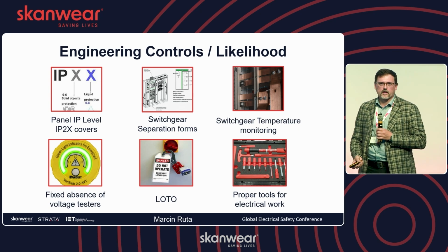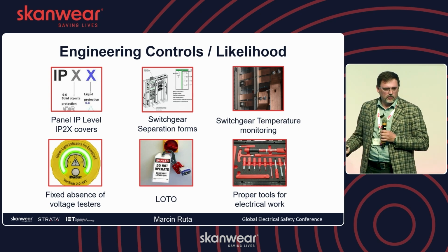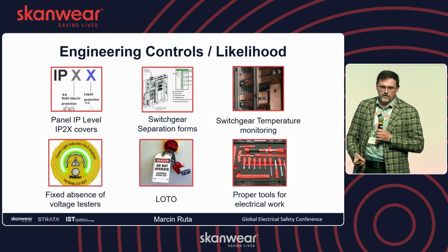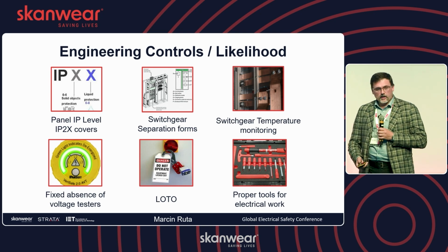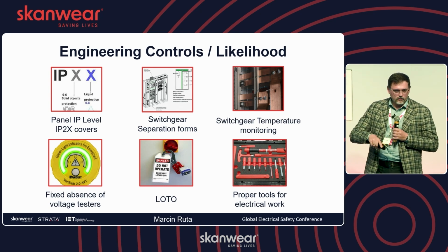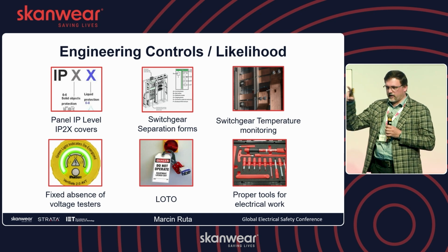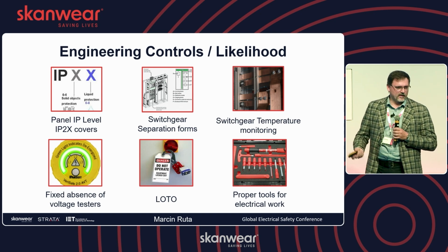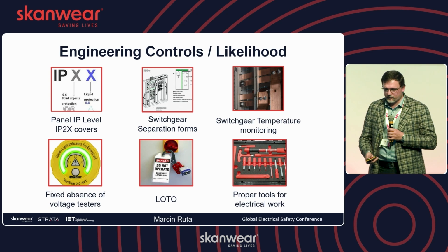Probably you will see it on medium voltage systems as a default, but on low voltage it's not really a default thing. Very nice to have. Lockout tagout, I mean not lockout tagout as a procedure, but you need to have a device that allows for lockout tagout, so you don't have to think around. Yeah, people are creative, but sometimes not that much.